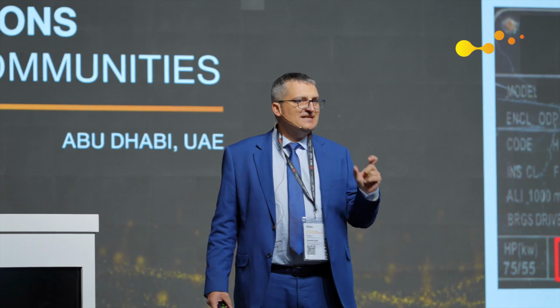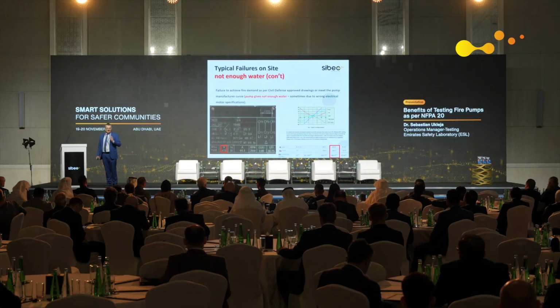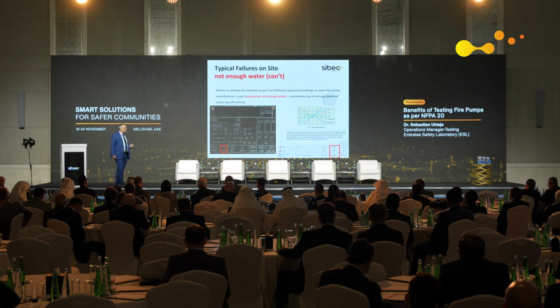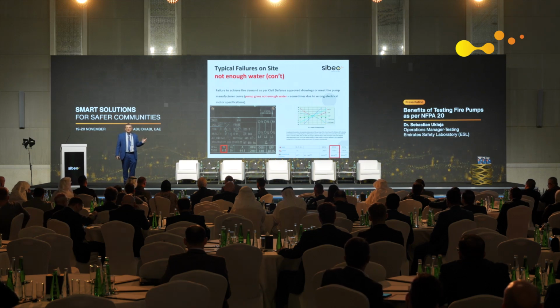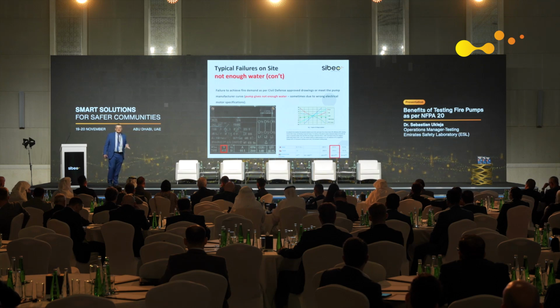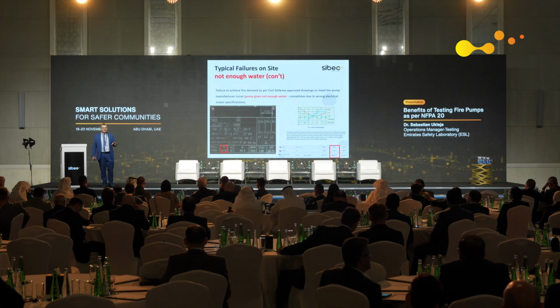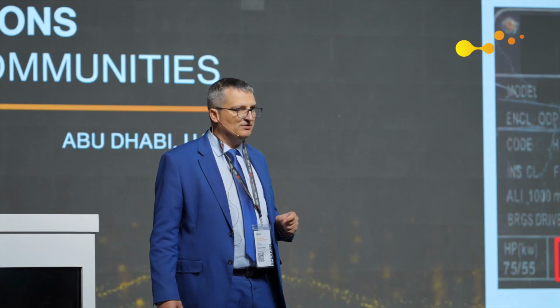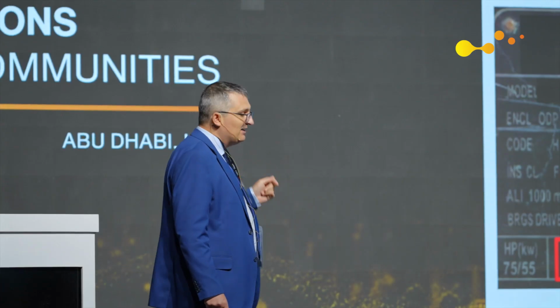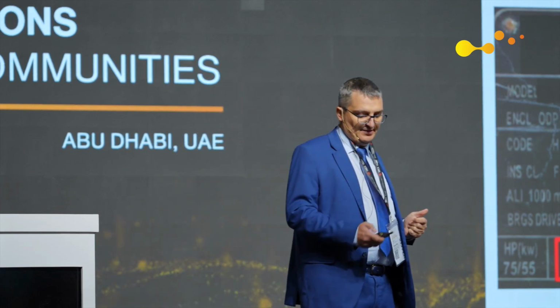However, if the pump is set for given requirements and whoever is buying the pump doesn't want to pay more, this is at least 5% loss on torque. And the pump, by this 15 volts drop, may not work properly. So if whoever specified the pump wanted to save a few dirham and buy the pump which is really for another country, it is not multi-voltage, which should be dual voltage, it will not perform the way it should perform.